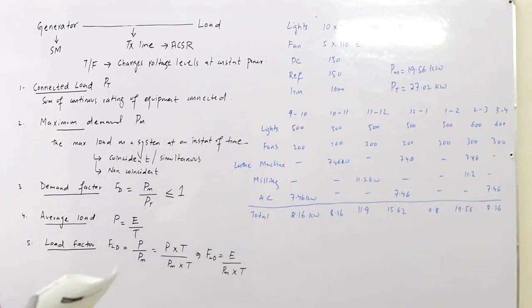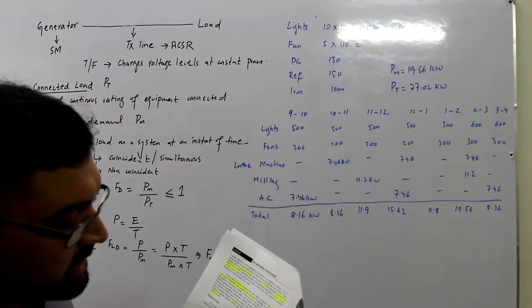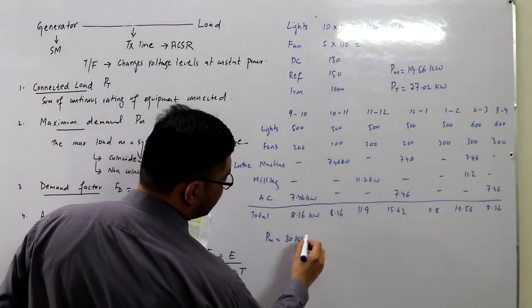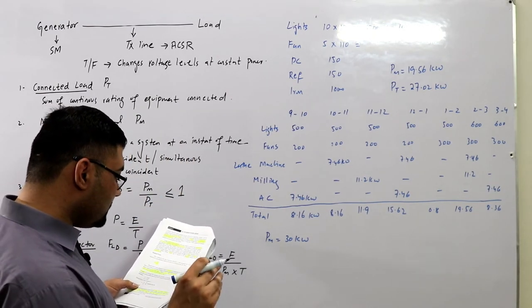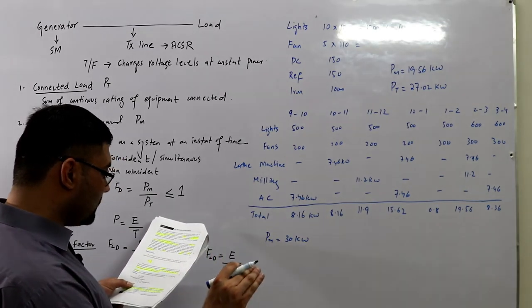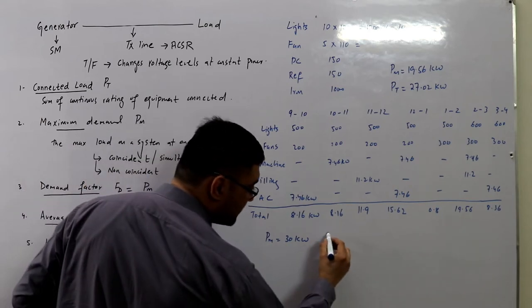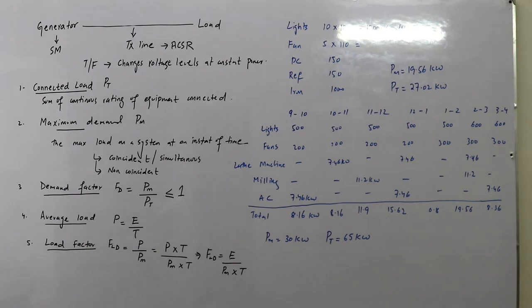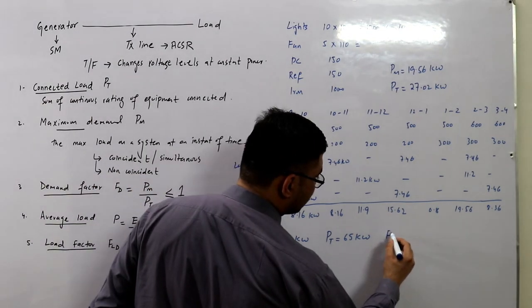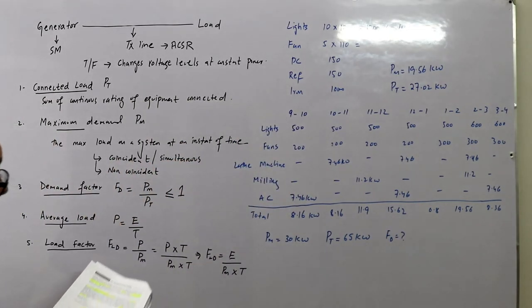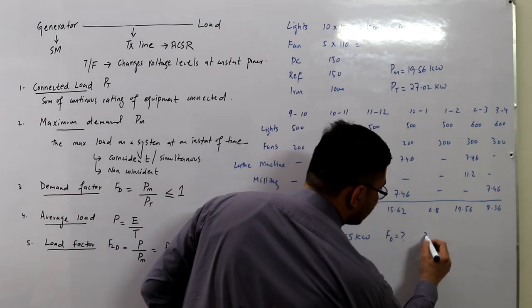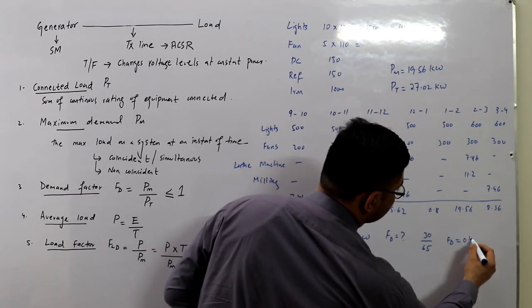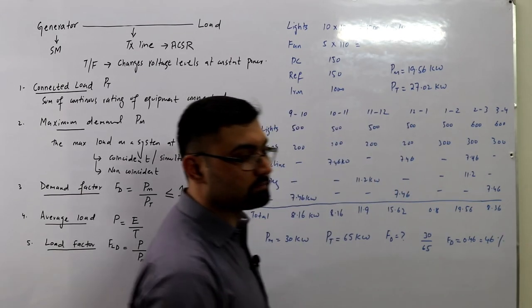Example: A consumer has a maximum demand PM of 30 kilowatts and equipment with an installed capacity of 65 kilowatts. Calculate the demand factor. FD = PM / PT = 30 / 65. The demand factor comes out to be 0.46, or 46 percent.